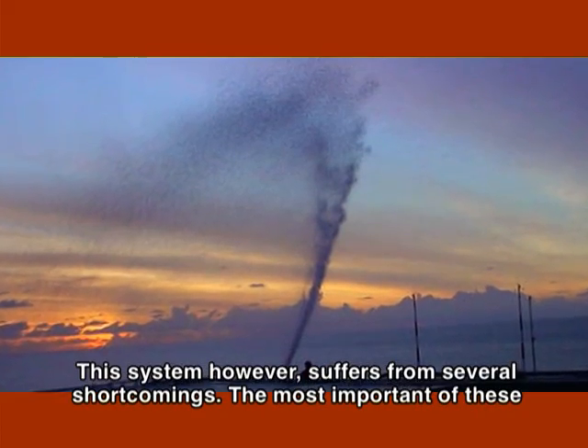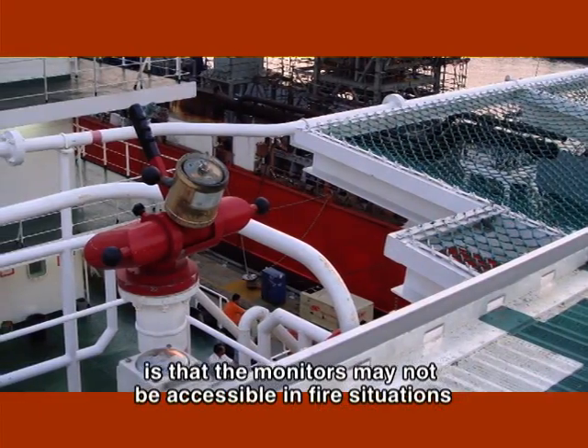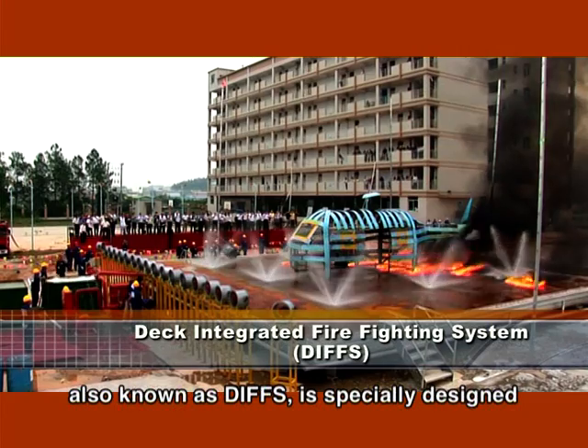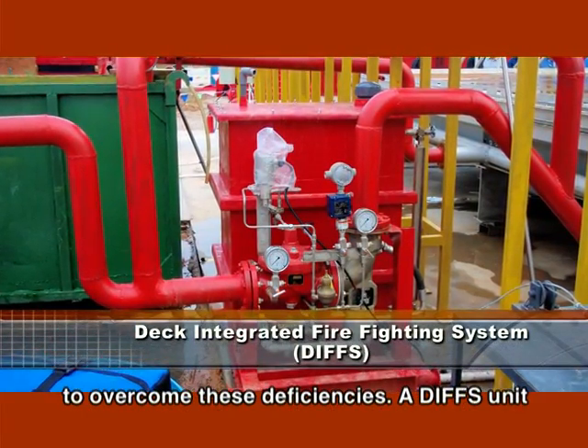This system, however, suffers from several shortcomings. The most important of these is that the monitors may not be accessible in fire situations because of the intense radiated heat. The new deck integrated firefighting system, also known as DIFFS, is specially designed to overcome these deficiencies.